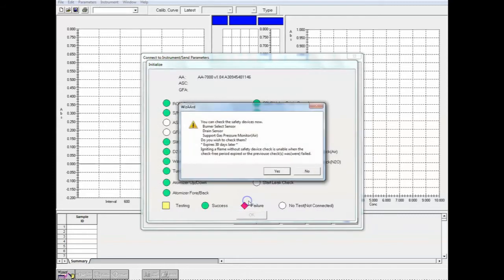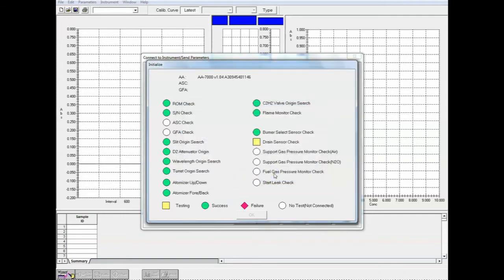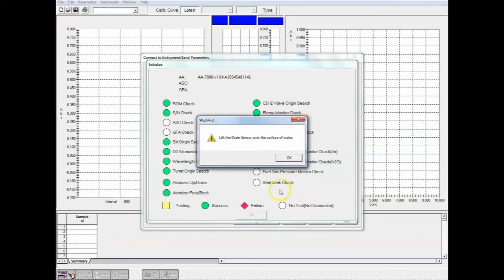Okay, done. Hit close. Now it wants us to check a few things. So it's asking us to check the burner sensor, the drain sensor, and the support gas pressure monitor. We can check all of those here on the actual machine. So I'll check all of those. I've already done that, and I'll select yes. Okay, so now it wants us to do a drain sensor. So I'll just go to the machine now and show you the drain sensor.